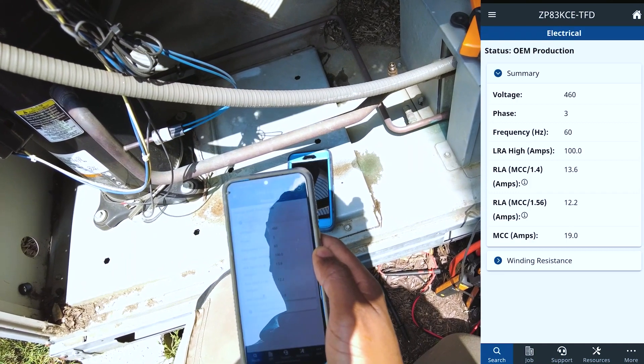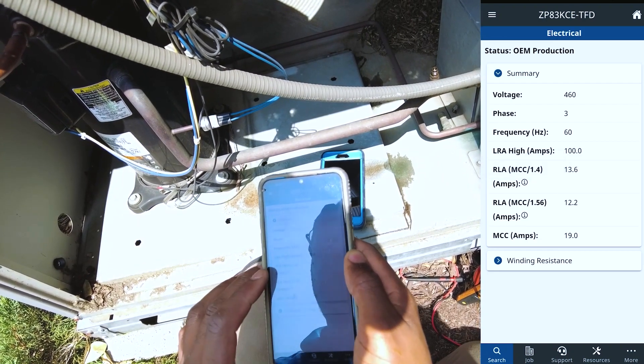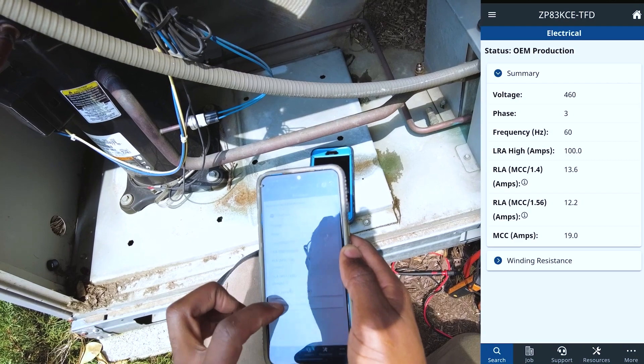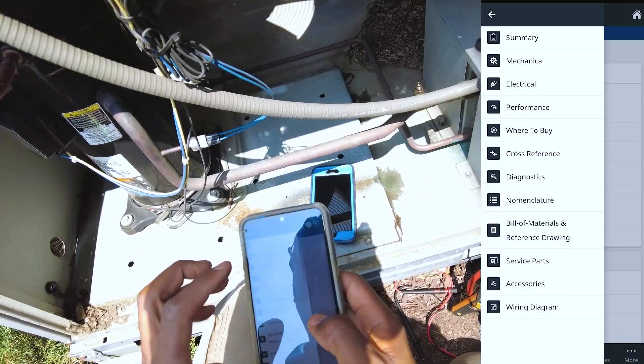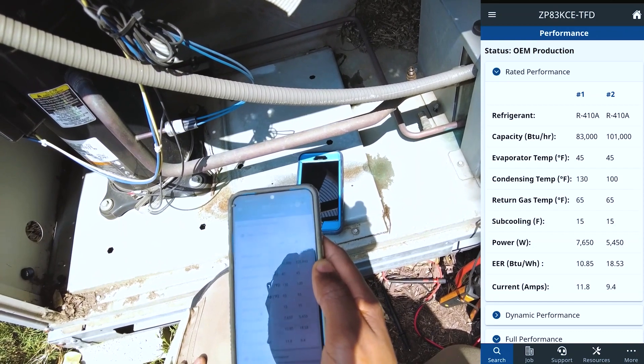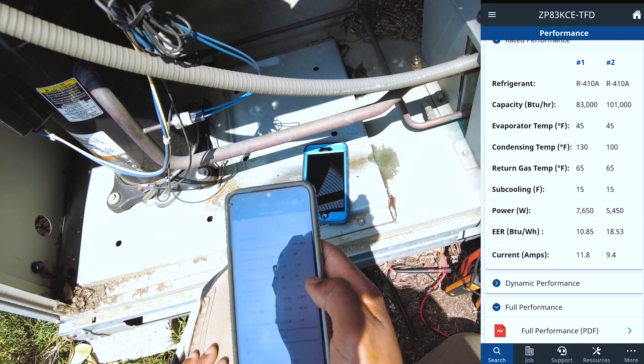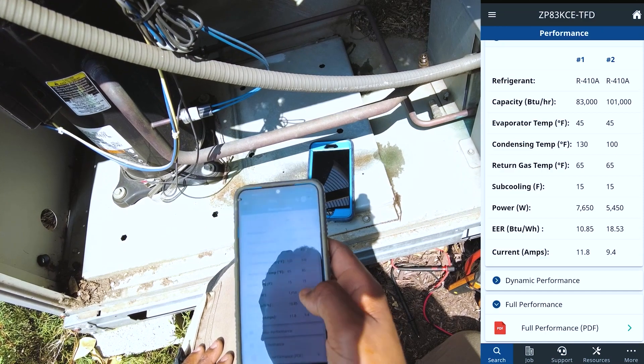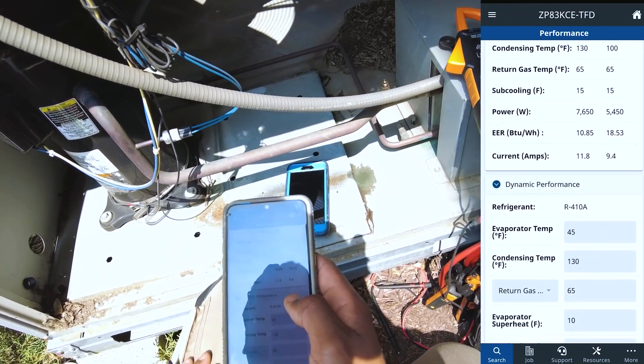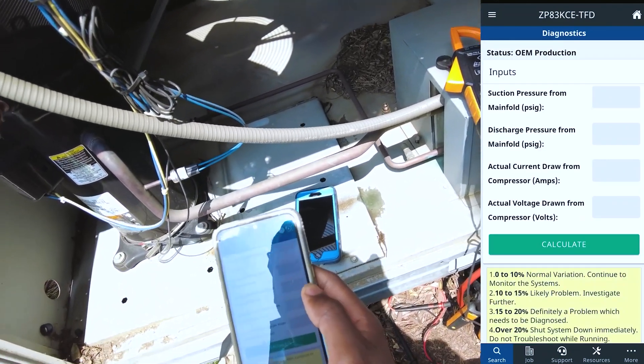Summary voltage is 460 volt, three phase, frequency 60 Hz, lock rotor amps, run load amps 13.6. You've got your winding resistance, which is really cool. And performance — rate of performance, condensing temperature, evaporator temperature at 45 degrees. See our dynamic performance — should have 15 degrees of subcooling.